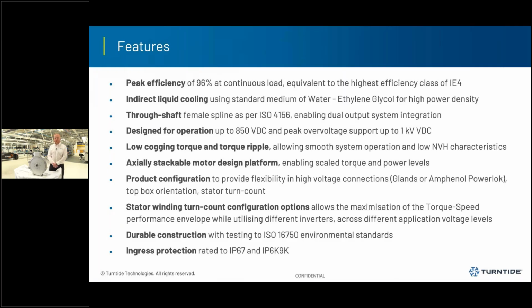We're designed for operation up to 850 volts DC, which meets the higher voltage classes we see in modern electrification systems, with peak over-voltage support up to 1 kilovolt.